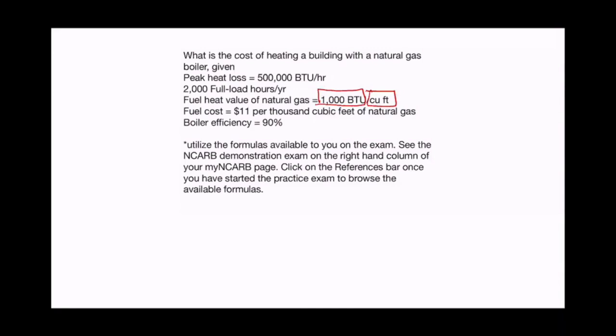So this peak heat loss is 500,000 BTUs per hour. That means on the coldest day we have calculated for our building, we're losing 500,000 BTUs per hour, which is enough to take 1 pound of water and raise it in temperature by 500,000 degrees, or to take 500,000 pounds of water and raise all of that by 1 degree Fahrenheit.